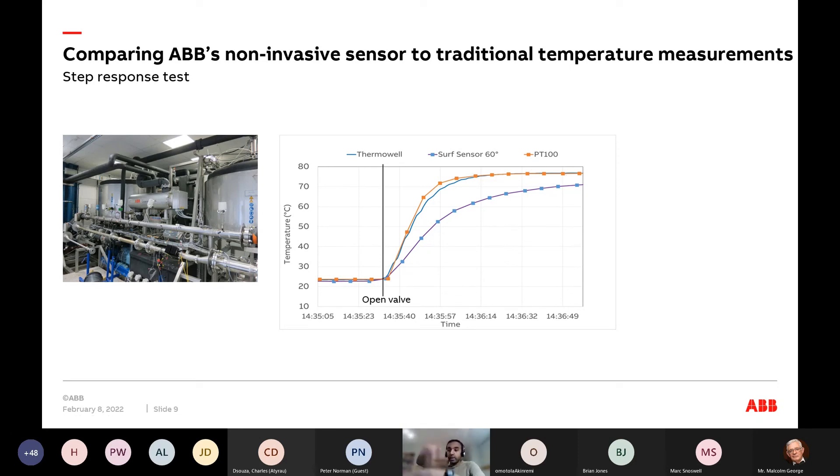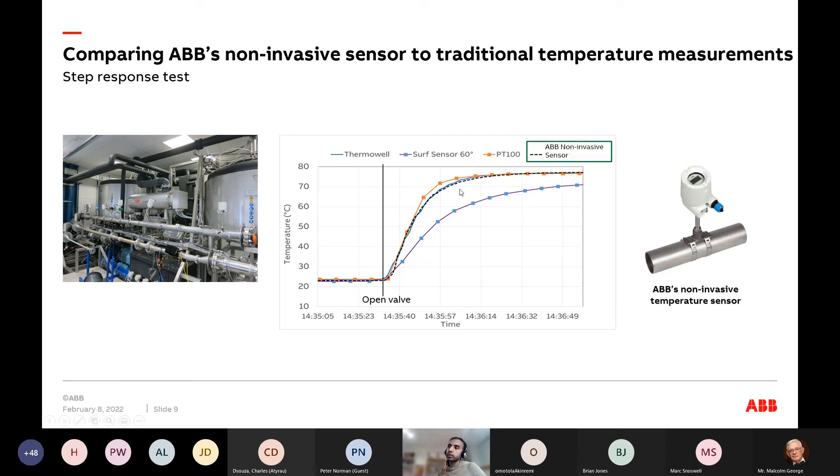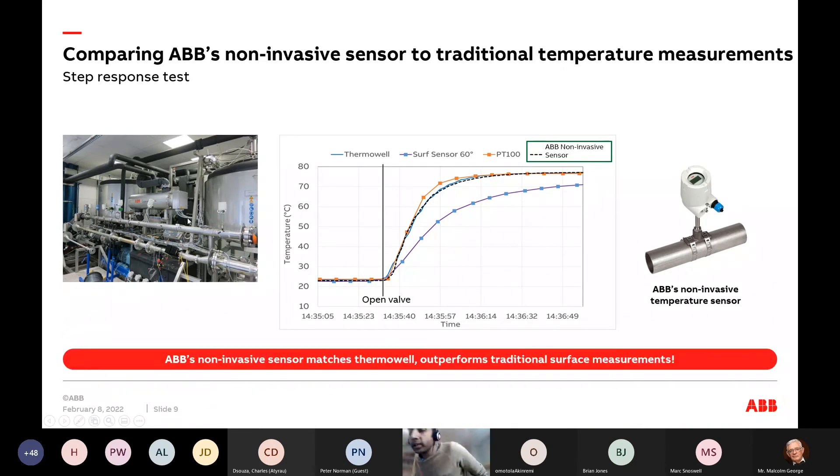Because we use the same principles with a single-point contact, our sensor response matches the thermowell performance. Our non-invasive principle matches thermowell performance because of the model-based approach. Even though we are using the surface, we are still turning that pipe into a sensor, and this approach can outperform any traditional skin temperature measurement you have.